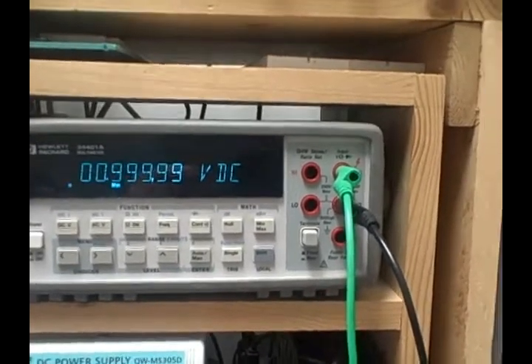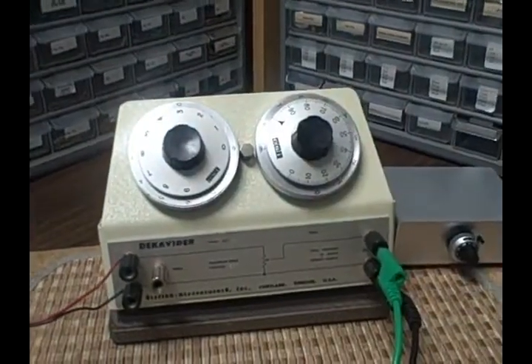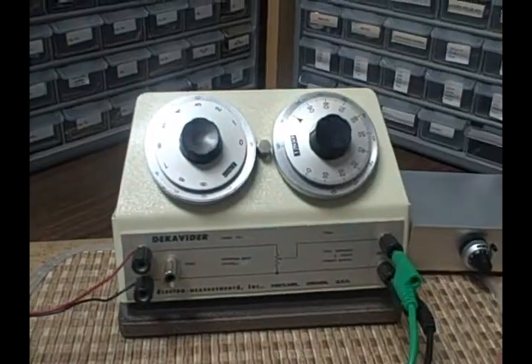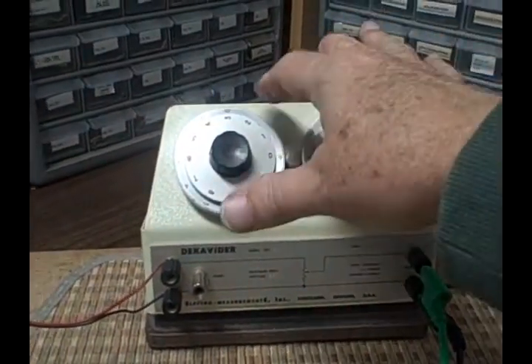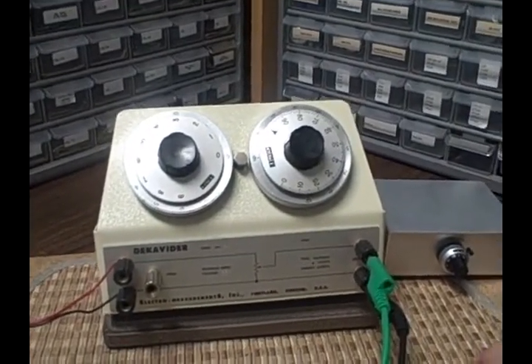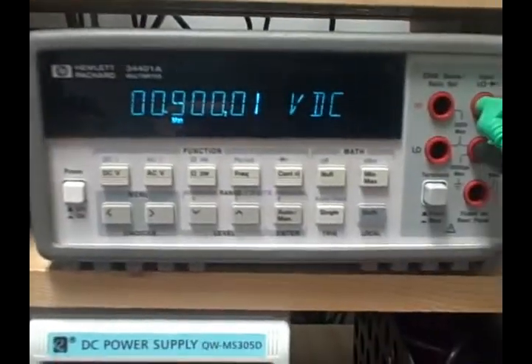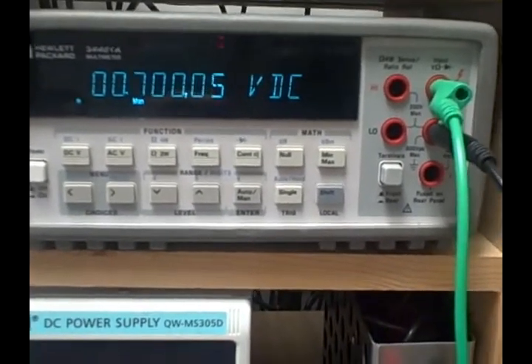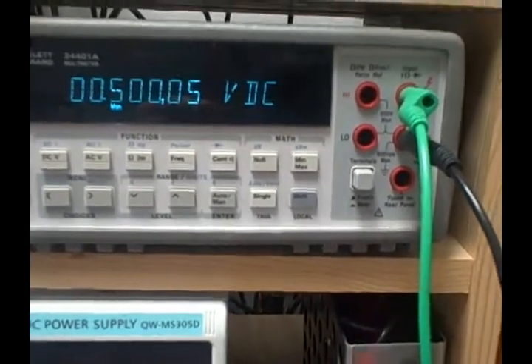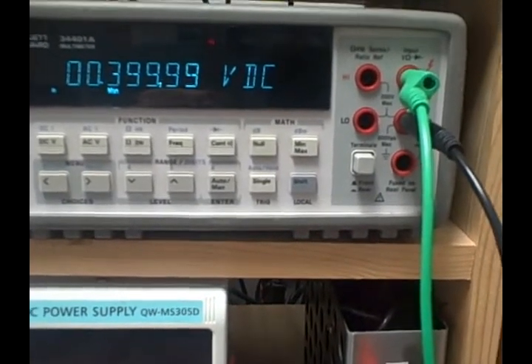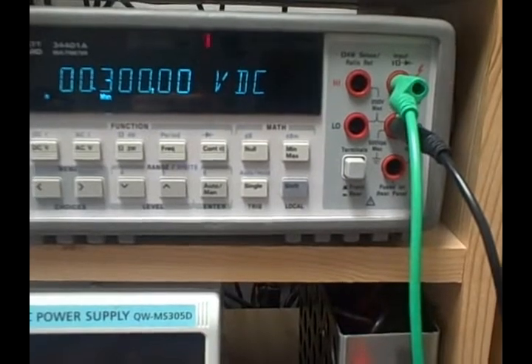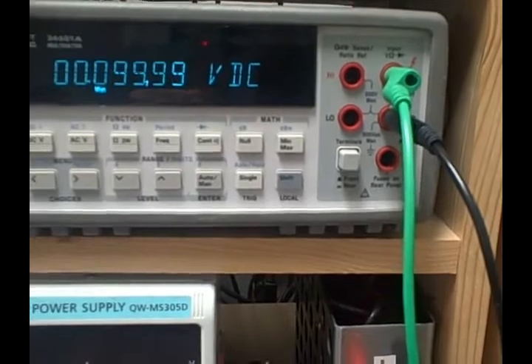All right here we are all nines. This is when the major dial is at zero and I'm now working in my second, third, and fourth and fifth decades. All right let's go to eight. All nine and pretty much all zeros. A little error there. Again what you'd like to see right now would be four in all nines. Three in all nines that's good. We've corrected. Two in all nines. One in all nines. Zero in all nines.